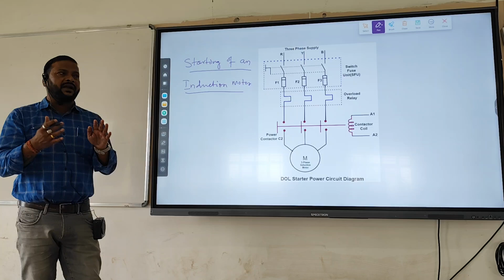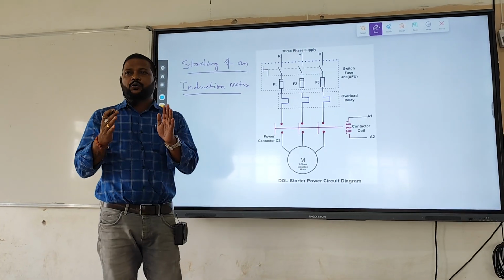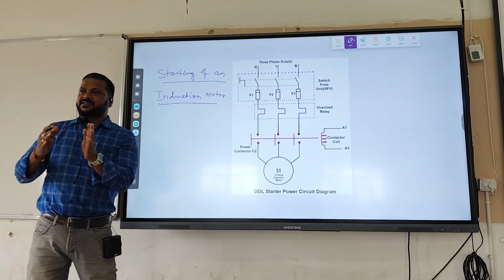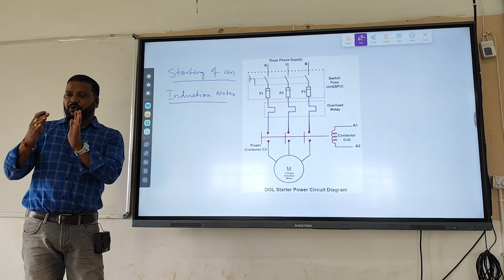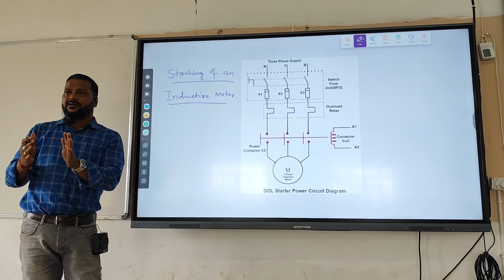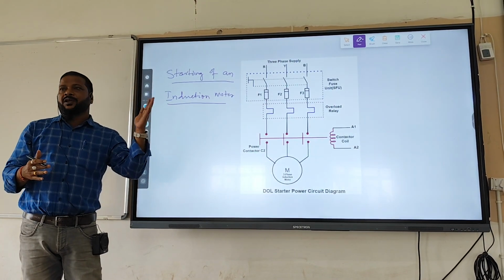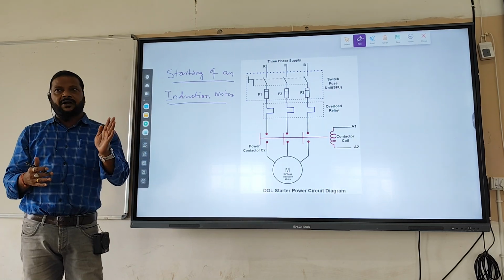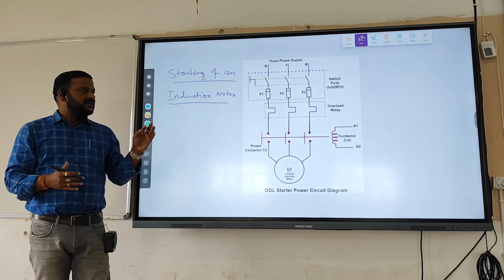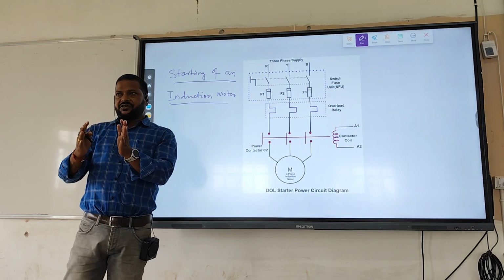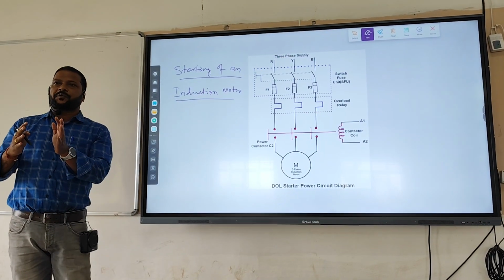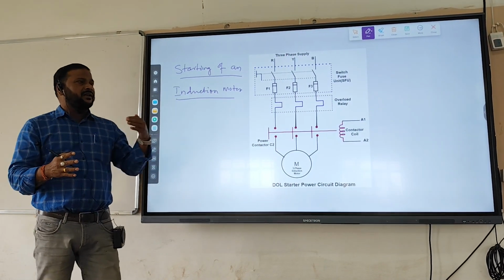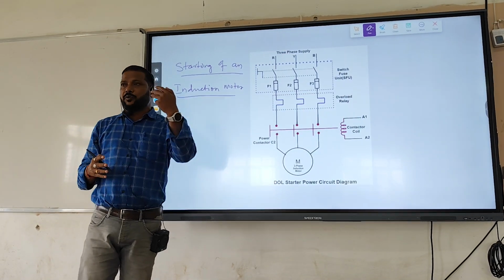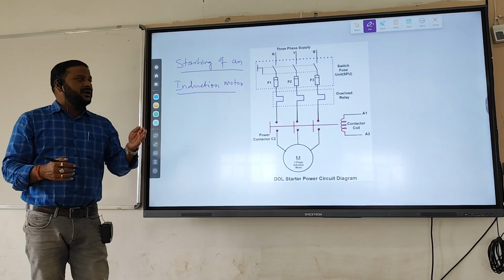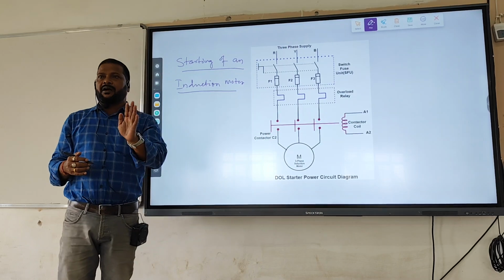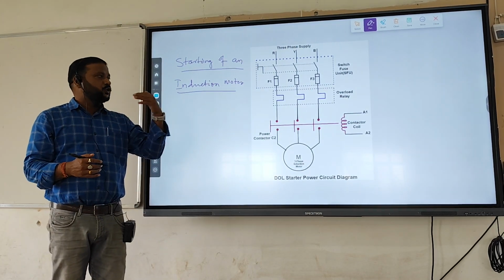So to avoid that, it is very essential to introduce one starter, that is a starting device, which is a protecting device, a safety device, before our induction motor, which can safely deliver the current towards the stator part of the induction motor. And the starter is a starting device along with a few safety protections. When abnormal current flows or overload occurs in the induction motor, it will simply give the braking command, or off command, or stop command to the motor.